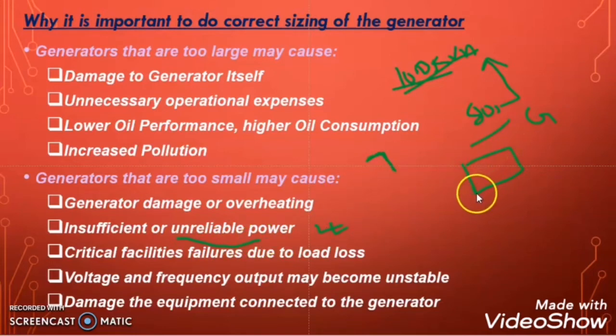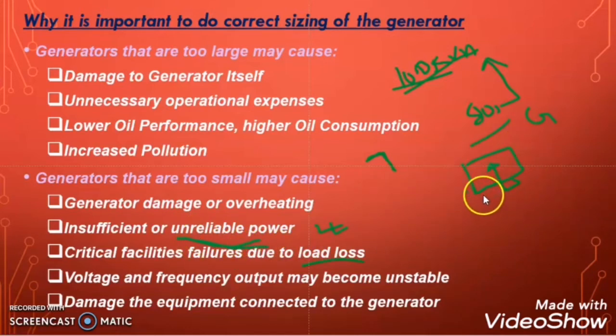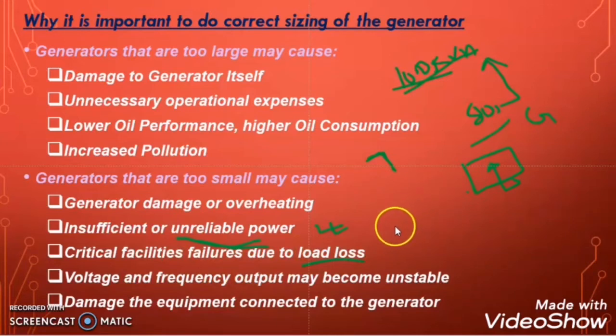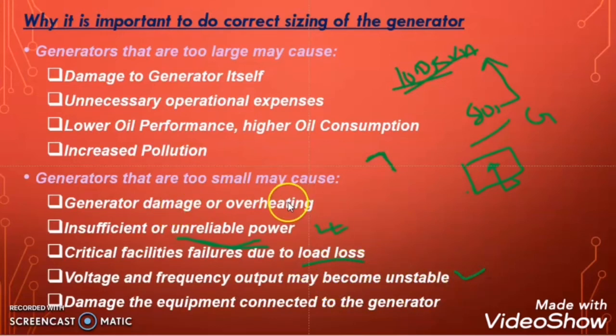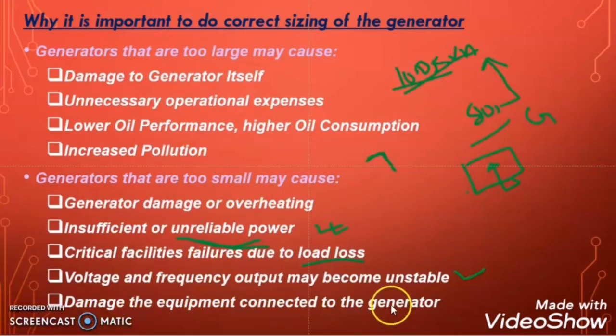Suppose you are doing some critical operation in the lab backed up by a DG set — due to overloading the generator trips, affecting that critical operation. Another point is critical facilities failure due to load loss; after overheating the generator will trip, creating a load-loss situation. Voltage and frequency output may also become unstable. Equipment connected to the generator can also be damaged. This is just an overview to understand why sizing the generator correctly is very important.